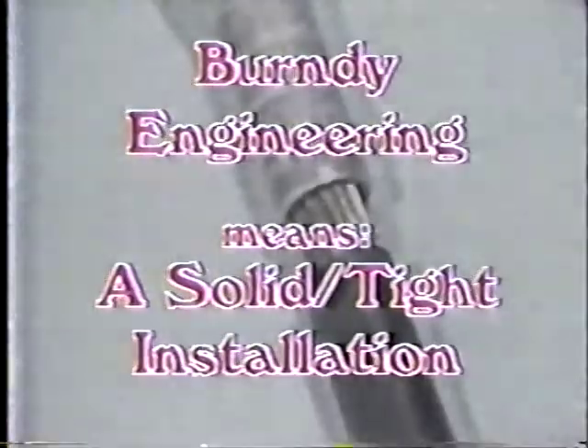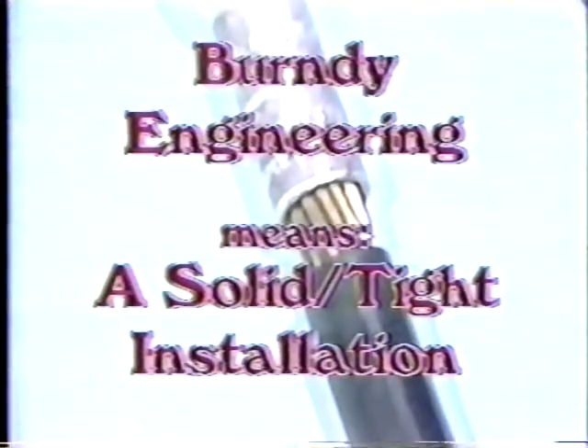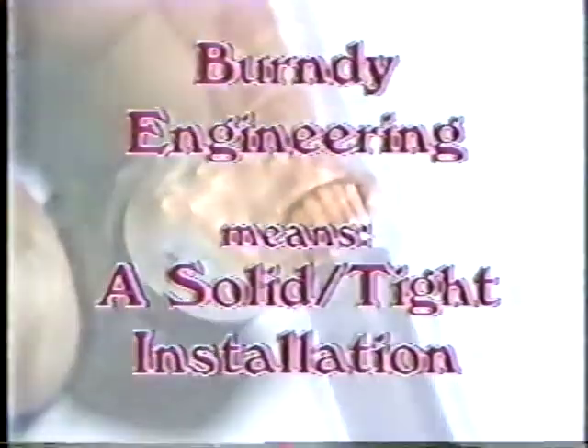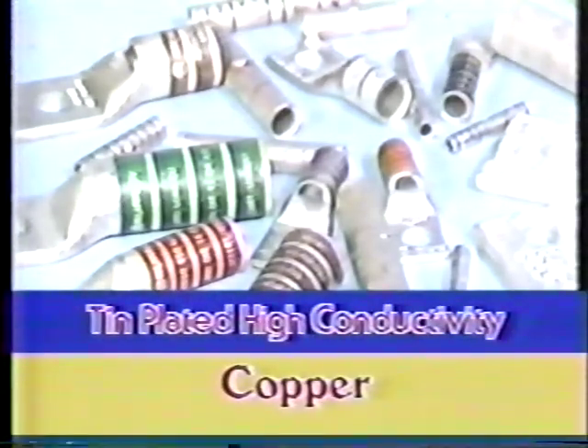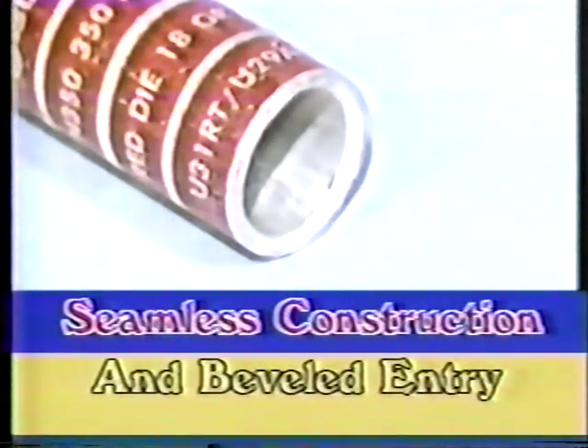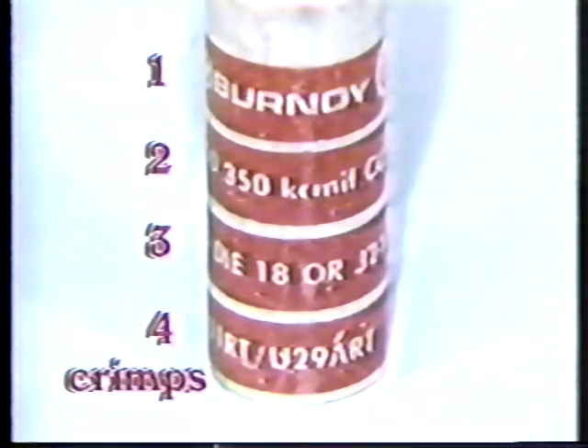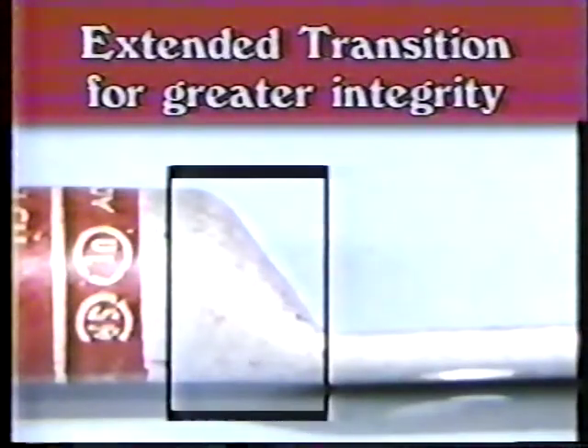Burndy connectors are engineered specifically to match the cable diameter, providing a solid, tight installation. Our comprehensive line of terminals and splices are made of tin-plated high-conductivity copper and feature seamless tubular construction with a beveled entry. The color-coded bands on the connector barrel indicate the position and the number of the crimps required for a proper installation. Burndy terminals also feature an extended transition, enabling you to insert all of the conductor strands past the crimp area for greater connection integrity.